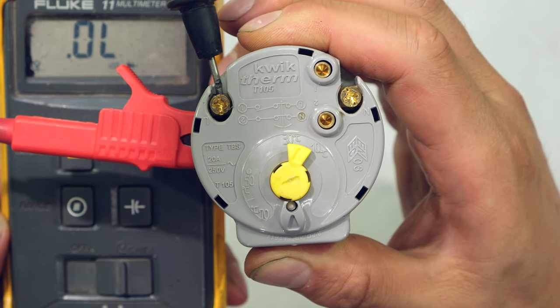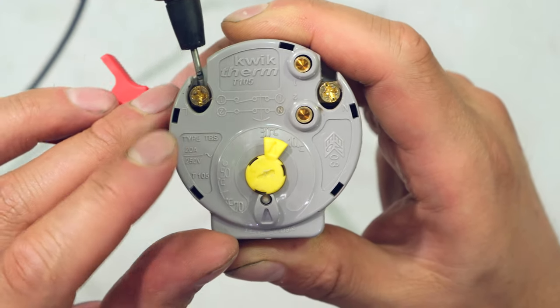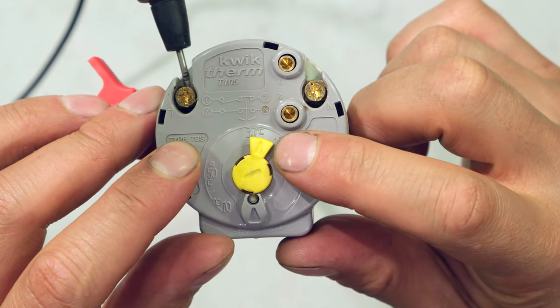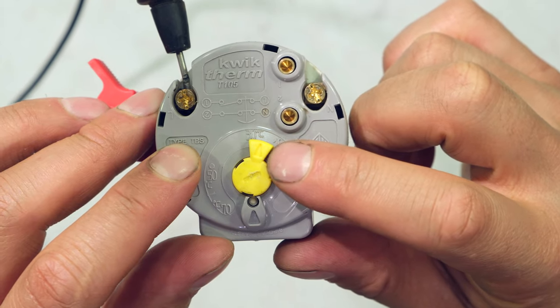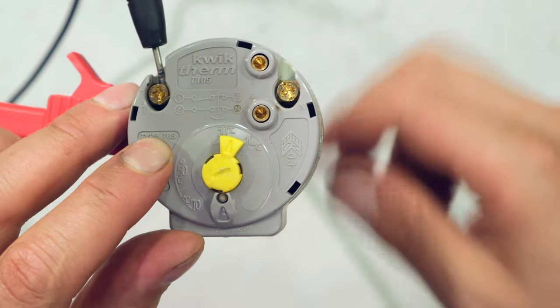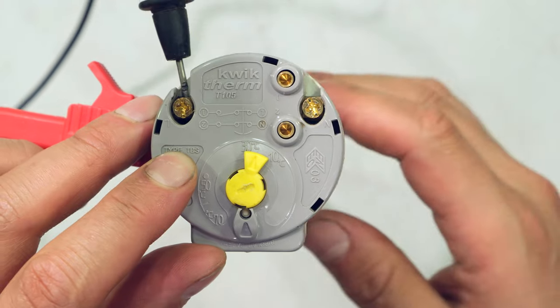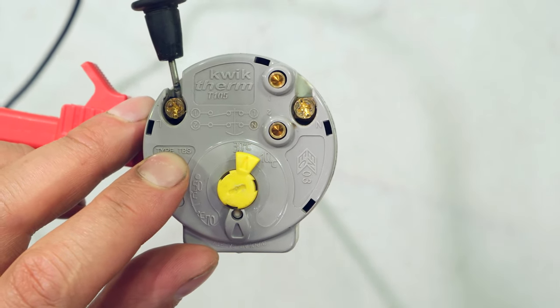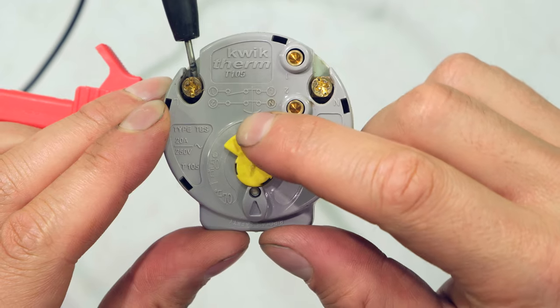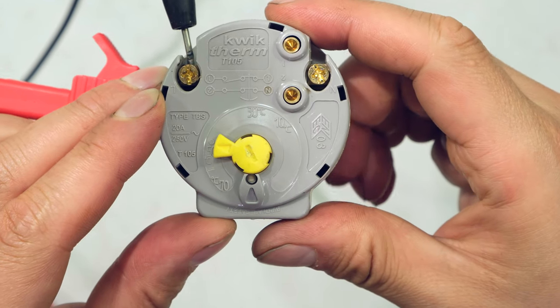And the reason why it's not going to allow current flow is the ambient temperature is already above the thermostat temperature, so it would not need to heat up anything. So let's test that now at a higher temperature. I'm going to set this to 50 degrees. Now I'm going to heat up the thermostat and the thermostat should open.